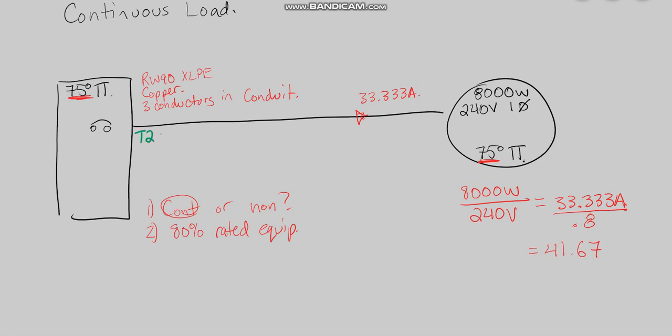Now that we have our 41.67 amps, we're going to go table two, 75 degree column, and we're going to size our conductor based off that 41.67 amps, which in this case should work out to a number eight AWG, which is good for 50 amps.